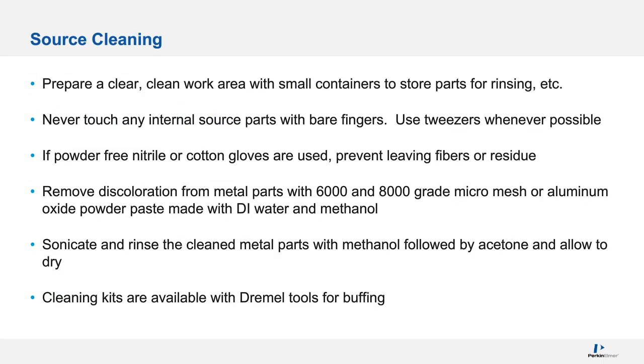Source cleaning, everybody has their own way. I'd rather just replace the parts that are dirty and throw them out. And typically I would just buy another source, but that has limitations. So I just make sure my whole area is clean. For cleaning a source, I do wear gloves because your fatty acids will give you problems later on. Use tweezers when possible to pick items up instead of your hands. Use powder-free gloves or cotton gloves that won't leave fiber on the source.